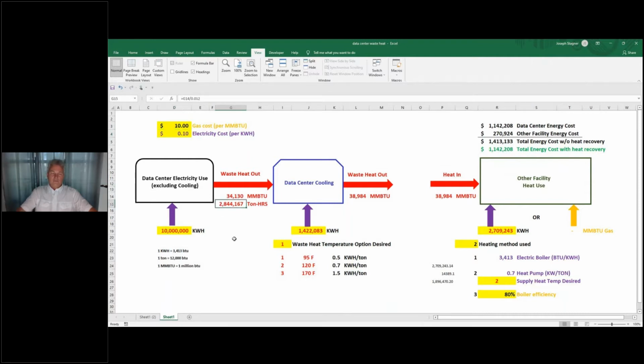And then you'd have to have cooling to remove that heat, which in chilling terms is 2,844,167 ton hours of cooling. So you go over to your data center cooling, and suppose you're using a conventional chiller, and you take that coolant and heat it up to 95 degrees to go out a cooling tower to be exhausted. Then you'd use about 0.5 kilowatt hours per ton in your chiller and cooling tower if you had brand new, current, clean, efficient machines. Some older chillers and cooling towers will use 0.7 kilowatt hours.